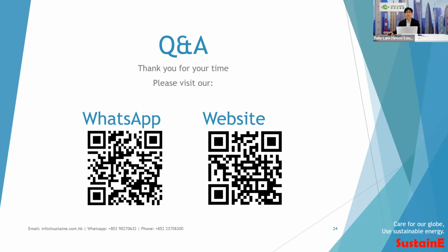But is there some kind of application in mainland China as far as you know? Yes, in mainland China, yes. In the colder regions they use a lot, because there the cost effectiveness is very good. In mainland China, especially in the north, the government gives incentives to replace the traditional heating system with the heat pump system. So yes, it is good in the northern part of China because the heating demand is large. However, in Hong Kong residential, the heating demand is not much compared to the northern part of China. Therefore, the cost effectiveness is not so attractive.